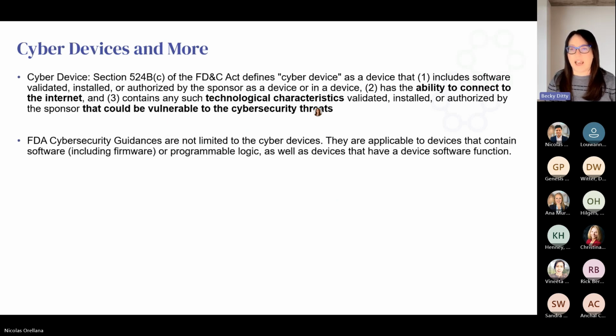FDA defines a cyber device, or the FD&C Act defines a cyber device as one that includes software by the sponsor, has the ability to connect to the internet, and contains technological characteristics that could be vulnerable to cybersecurity threats. However, it's important to note that FDA cybersecurity guidance documents are not limited to cyber devices, because even if your device doesn't connect to the internet, it still has cybersecurity risks to it if it's got software, if it's got ports, if the software can be updated, if it has programmable logic. So cybersecurity guidance documents go above and beyond just cyber devices. Typically, if you have software, you have cybersecurity concerns.